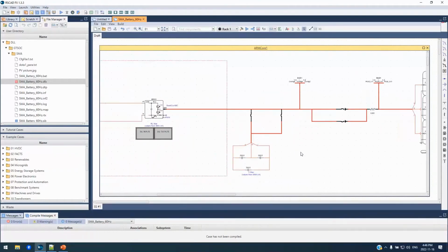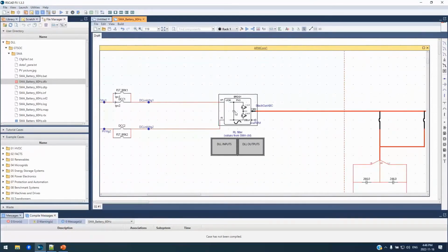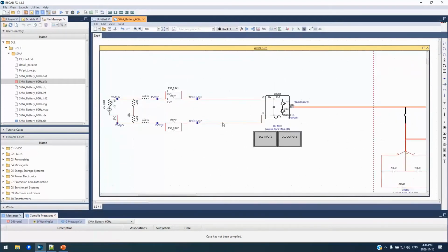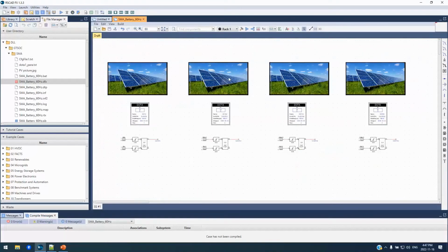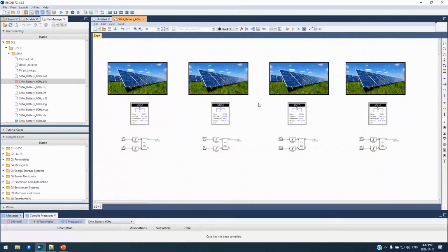So then on the inverter side, we have the filters. We have our capacitor filters. Our RL filters are inside our inverter component, and we have some breakers. Here we have our UCM two-level inverter model, and that's converting the DC to AC. And then on the DC side, this is a battery case, so we've simplified the battery to just a DC source. We have some inductors, and then we have a breaker on the DC side as well. Like I said, in the other hierarchy box, we have the identical circuit, just changing the names. This is just to test all 4 SMA inverter controls on GTSOC.